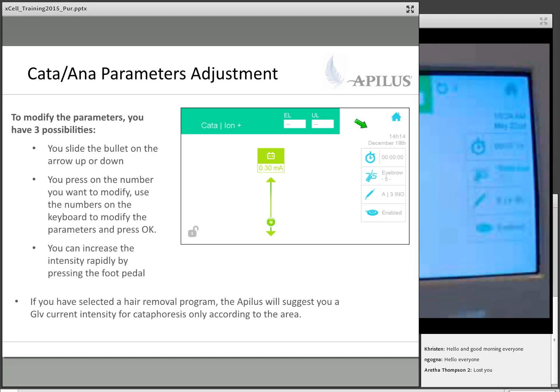Then you come back and you start to do cataphoresis on the eyebrow. But the last setting you had was a bikini setting. So the machine will put in bikini level of MA, which would be too high for the eyebrow and can definitely be a little bit more painful for the client. So keep that in mind. You might want to go in here and put in the appropriate body part, or you just change it manually.